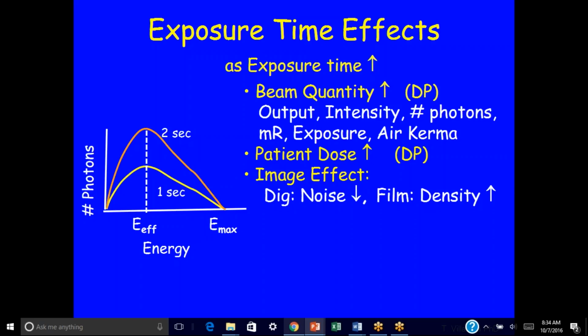And as time goes on, the techs would again, for one reason or other, if they have a higher exposure, say, hey, this looks even better. From now on, we'll give it a little bit more exposure time. That's dose creep. And it was found, where it was studied, almost invariably from institute to institute. People were giving a little bit more dose every year. The dose was creeping up, because more dose means less noise means better looking images. So dose creep. There is going to be a limit to how much time you give. Remember, the exposure time you give also affects motion.